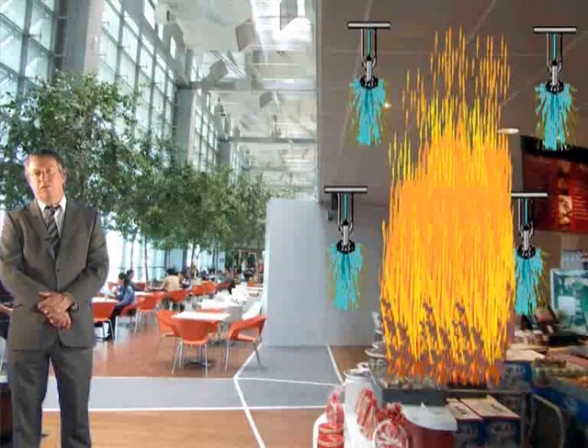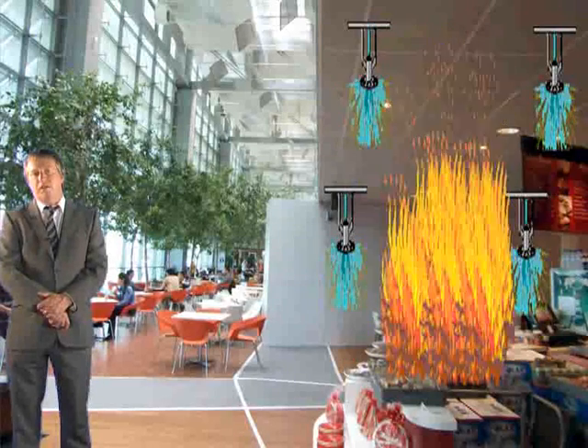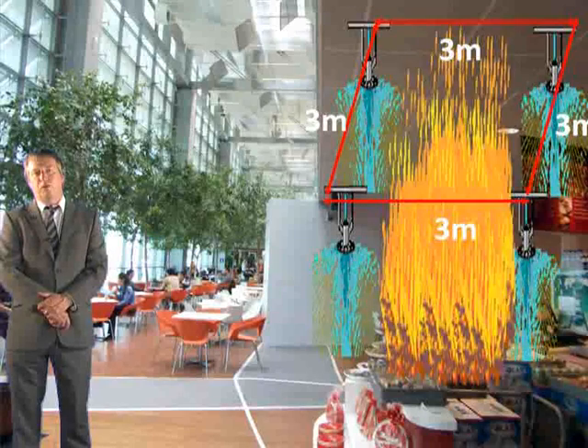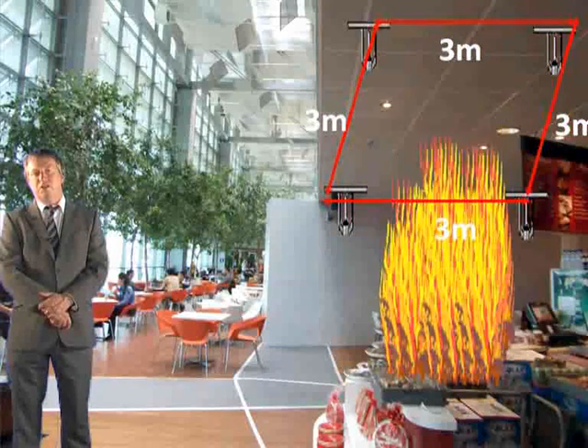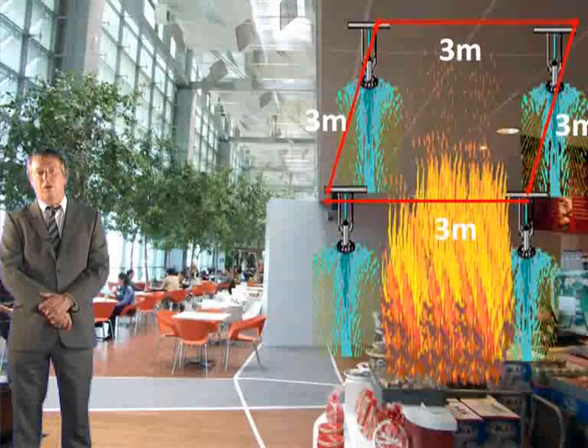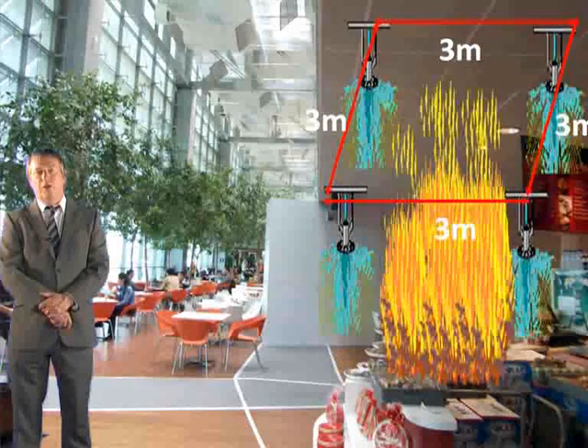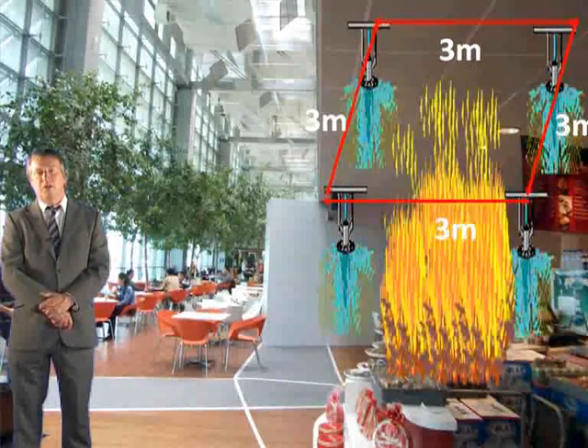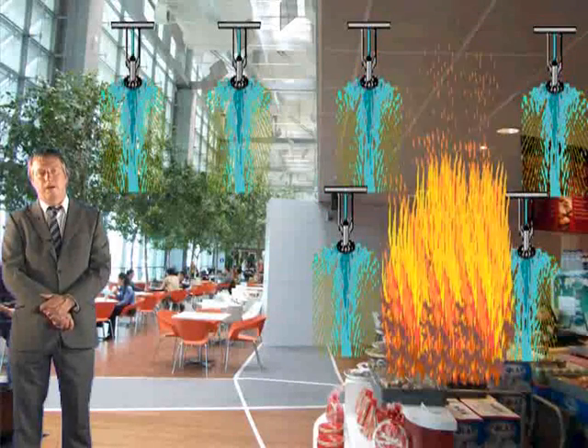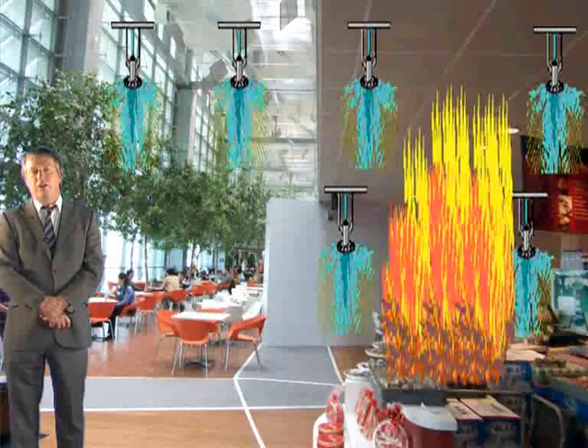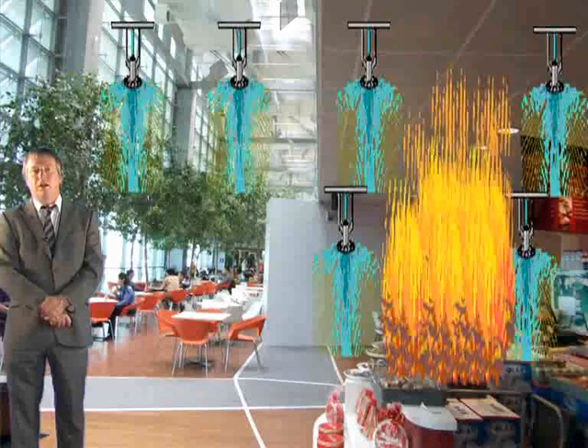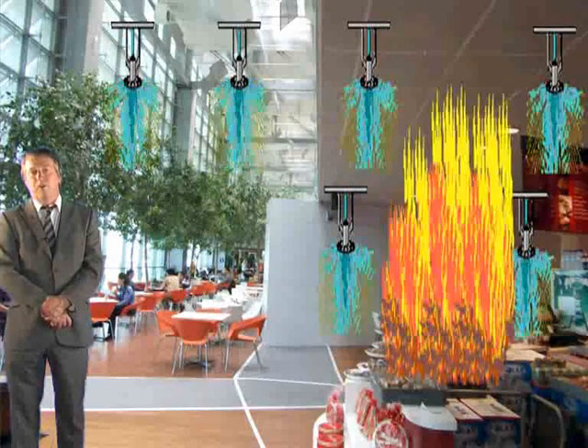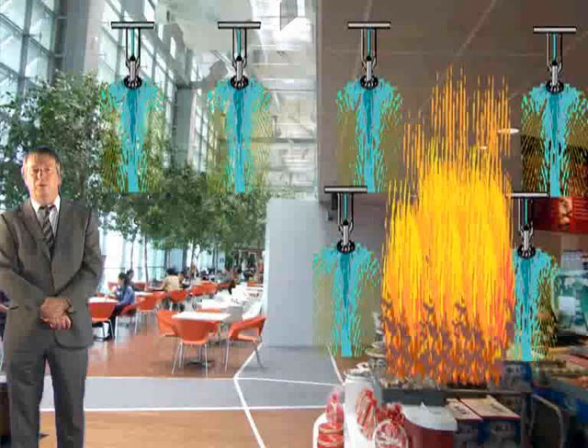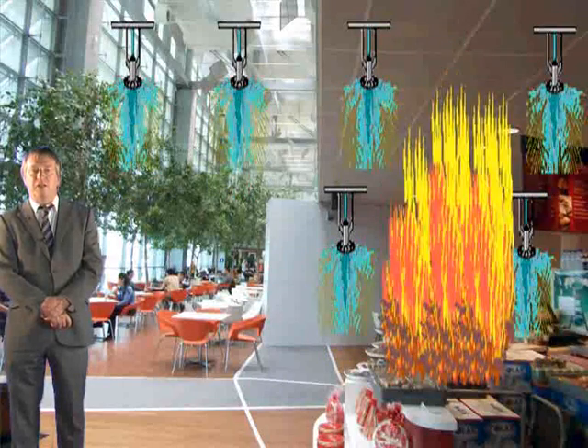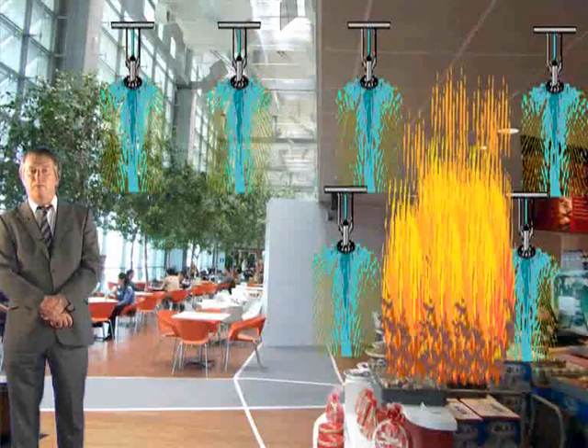That is, if the sprinklers are set in an array with 3 metres between the sprinkler heads in each direction, then the maximum size that the fire will be expected to grow to will be 3 metres by 3 metres, which is 9 square metres. There may well be sprinkler heads other than the 4 immediately surrounding the fire that are also discharging water, but they'll be wetting the surrounding area, stopping it from burning, and the fire will be contained to the space within the 4 heads around the point of ignition.